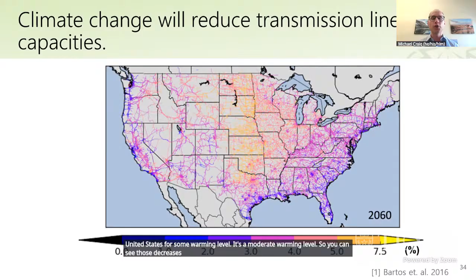This happens because transmission line capacity, or how much power can move through them, is a function of weather variables: temperature, solar radiation, and wind speed. It's essentially a heat balance in your conductors. Higher temperatures and more solar radiation heat up the line, just as they would heat you up, while wind cools the line off. So higher temperatures and more solar radiation mean more heat and less capacity, while more wind means more capacity.